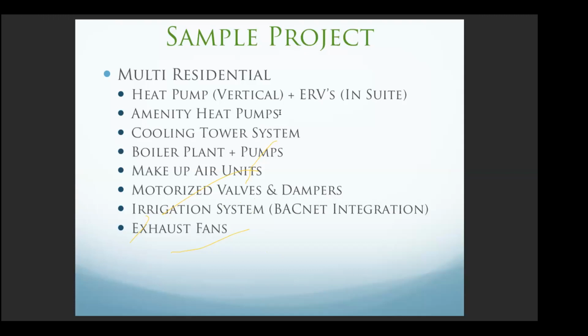There's amenity heat pumps. Now in this scenario, in an apartment building, there are amenity areas. There may be some office conference rooms, for example. There may be a gym. There may be a spa, etc. So all of these things are being served by amenities. The heat pumps in the amenities are typically horizontal heat pumps. They will have a BACnet controller on them, either from the manufacturer or installed in the field by the controls contractor. And there will be a thermostat wired to this controller.